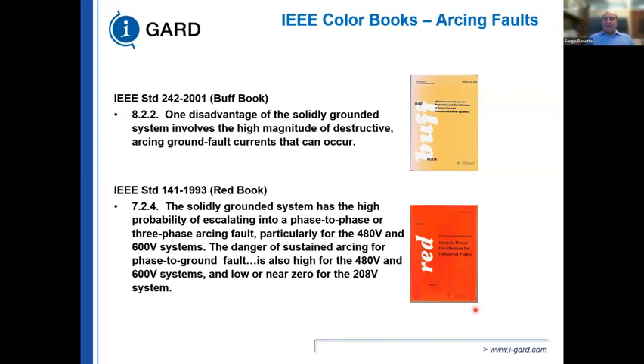You can easily get 20, 30, 40,000 amps in a ground fault. And the National Electrical Code, either the Canadian Electrical Code or the National Electrical Code in the US, state that you have to trip when you have a ground fault on system voltages greater than 150 volts to ground, greater than 1,000 amps. So if you have a system that's greater than 150 volts to ground, you have to have ground fault protection. And as engineers, we always try to strive to meet the minimum requirement. So when we have ground fault protection, we put it on the main breaker. You have a ground fault, you trip the main breaker.